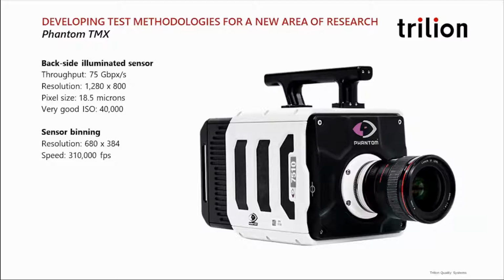So traditional CMOS sensors have a front-side illuminated sensor. What happens is when photons impinge upon that sensor, they must go through a metal wiring architecture before hitting a photoactive substrate. Back-Side Illumination technology basically flips that on its head, and those photons can immediately interact with that photoactive material, and then those electrons are collected behind the sensor. With this type of architecture, you get better fill factor, so you can utilize that sensitivity, because when you're working at such high frame rates and such short exposure times, you need that extra sensitivity to be able to see things with such short integration times.